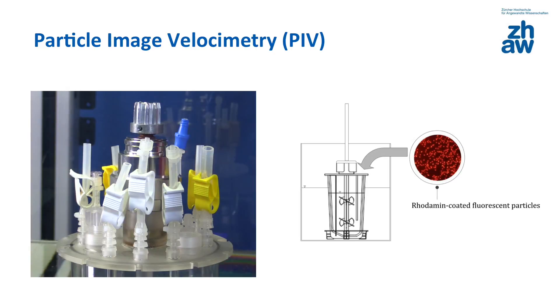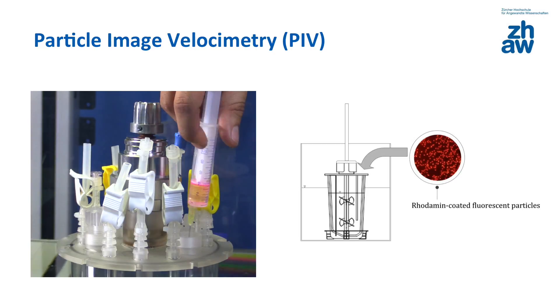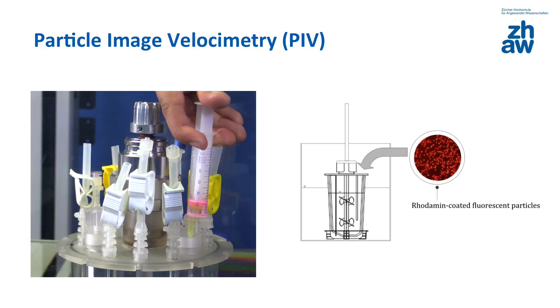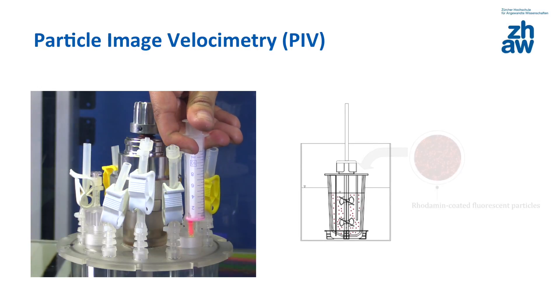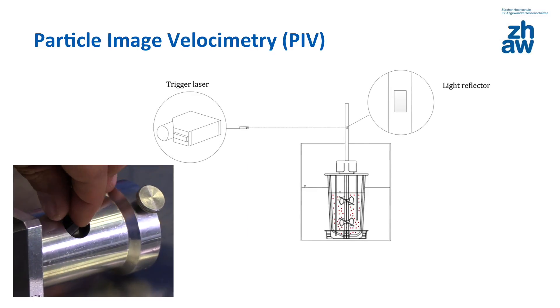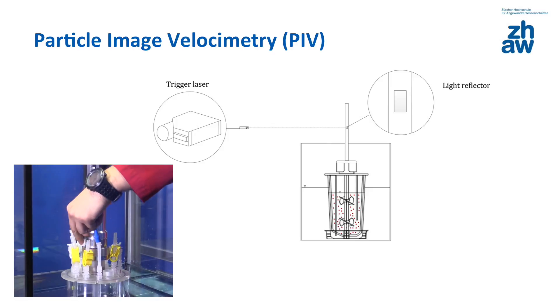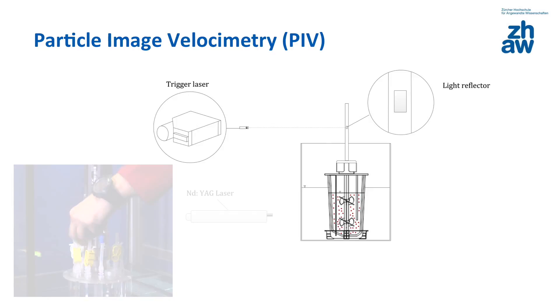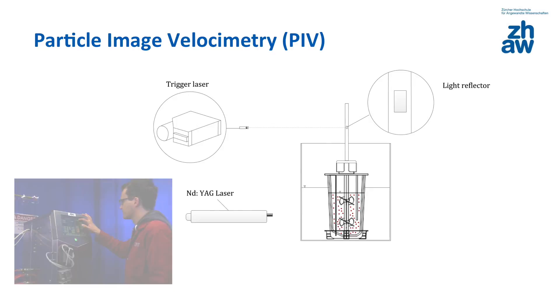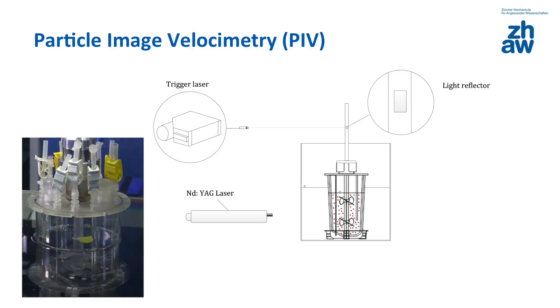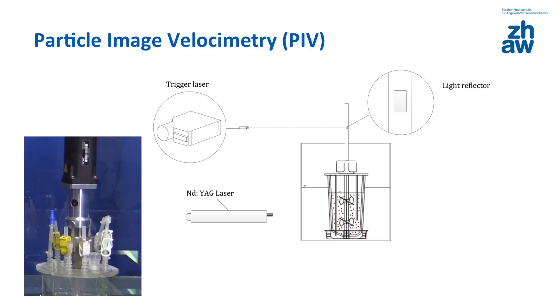Rhodamine-coated fluorescent particles are then added to the Univessel. The particles follow the fluid flow mostly slip-free, absorbing the green laser light and emitting fluorescent light which is simultaneously recorded. After putting the bioreactor in position, a reflection marker is placed on the bioreactor shaft. In combination with the trigger laser, the reflection marker allows phase-locked measurements to be made.